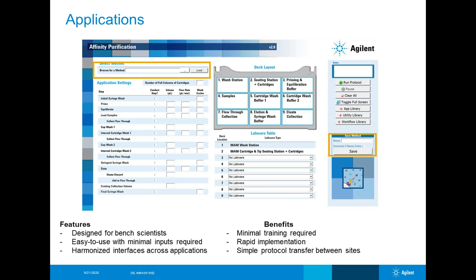We also have a Peltier on the deck. For in-solution digestion we want to keep our reagents at a certain temperature, so we use the Peltier for in-solution digestion, on-cartridge reactions, and glycoprep glycan protocols. There are a lot of different deck components that enable all the different workflows. It's very easy for a bench scientist to pick it up and go right into working on the AssayMap Bravo.